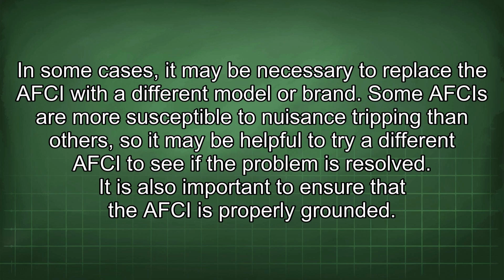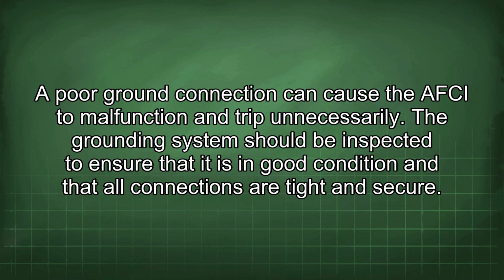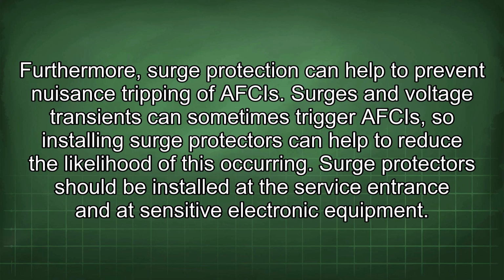It is also important to ensure that the AFCI is properly grounded. A poor ground connection can cause the AFCI to malfunction and trip unnecessarily. The grounding system should be inspected to ensure that it is in good condition and that all connections are tight and secure. Furthermore, surge protection can help to prevent nuisance tripping of AFCIs. Surges and voltage transients can sometimes trigger AFCIs, so installing surge protectors can help to reduce the likelihood of this occurring. Surge protectors should be installed at the service entrance and at sensitive electronic equipment.